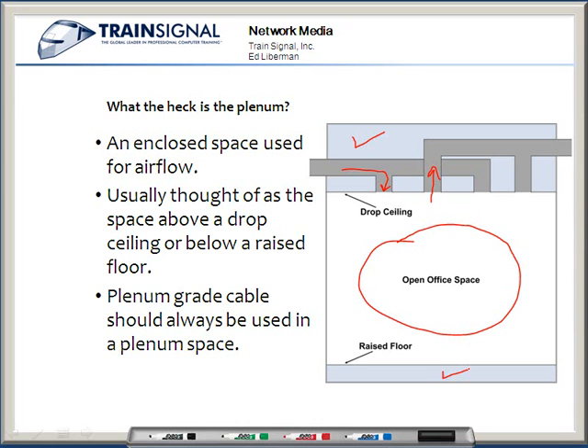Although technically they may not be the plenum, you may want to use plenum grade cable in those empty spaces. If we go back to our drawing, even though we may have designated space for airflow, over time a hole may form in the duct - that happens all the time. Then air from this open space leaks into that ductwork.